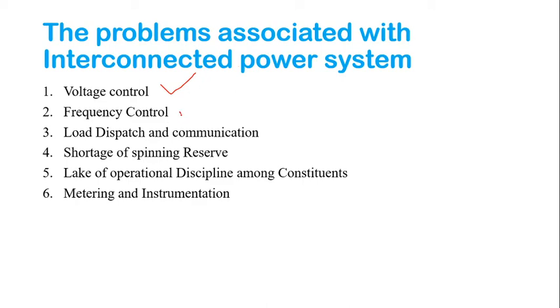Now the second one is frequency control. It is known that for proper system operation, the system frequency should be maintained at least between 48.5 hertz and 50.5 hertz. This is where we need to maintain our frequency level. In some cases during peak load conditions, the frequency tends to be very low, about 48.5, and in average loading conditions, when the peak load is off, the frequency can go up to 50.5. Under this condition we can use a frequency relay for automatic load scheduling, from which we can adjust our load and connect new generating units in parallel. That's how we can rectify frequency control.